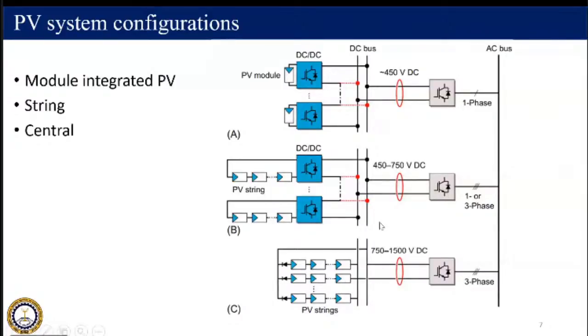Now each of these systems has its own advantage and disadvantage. When it comes to the central inverter, there is only one power electronic converter and the complexity is less. But the problem is that the DC bus voltage is very high, and the DC cables have a higher cost as compared to AC cables, and operating at this high DC voltage is not safer. But the advantage is that only one inverter has to be controlled.